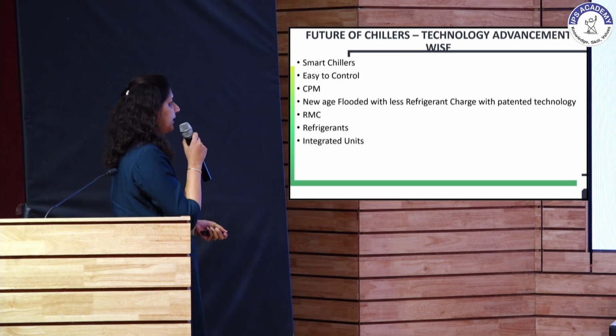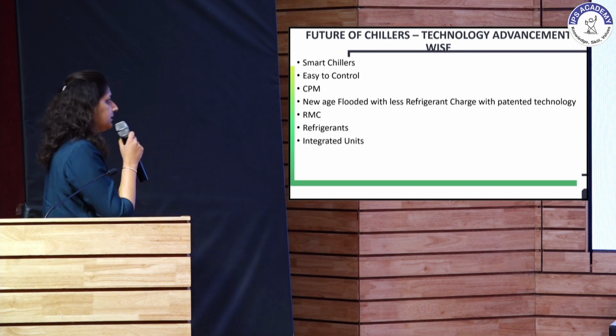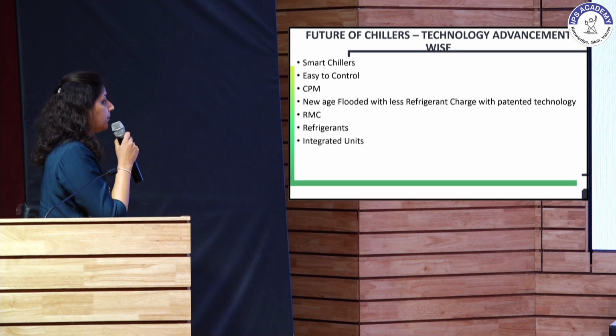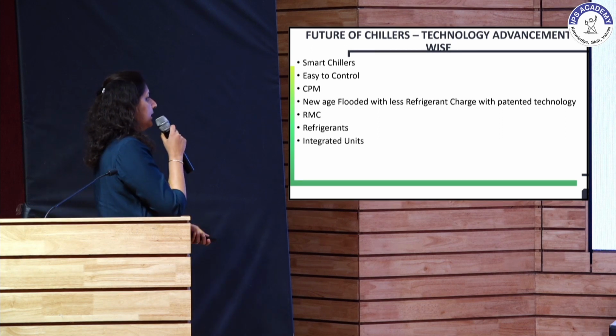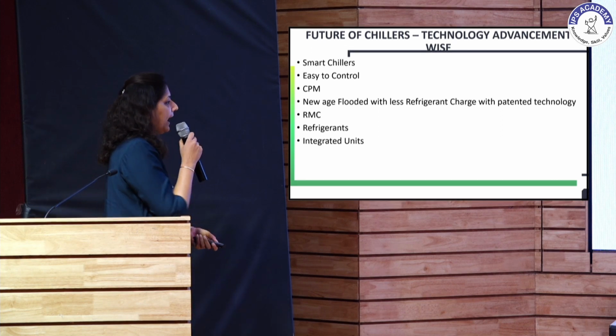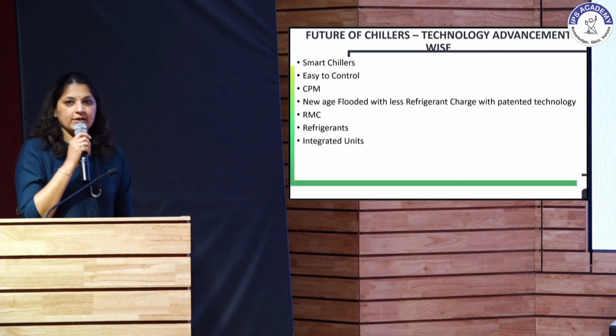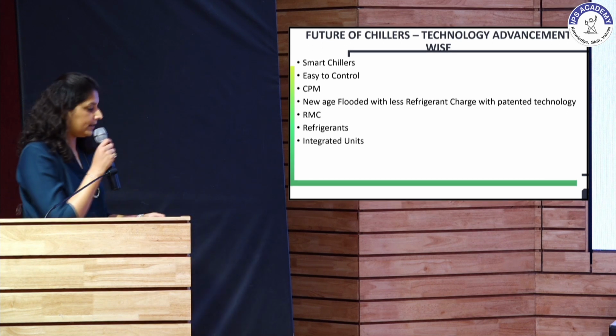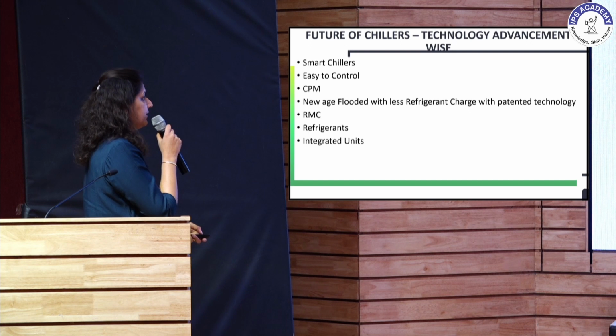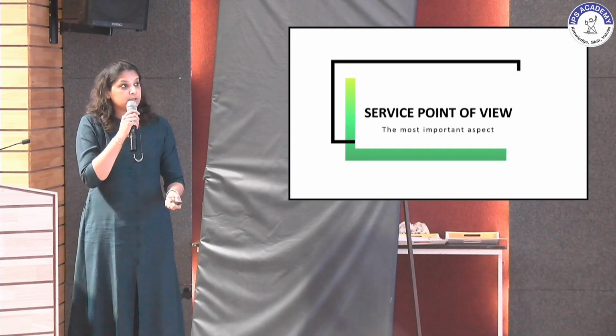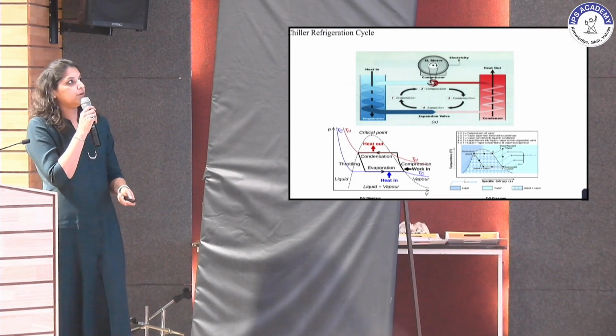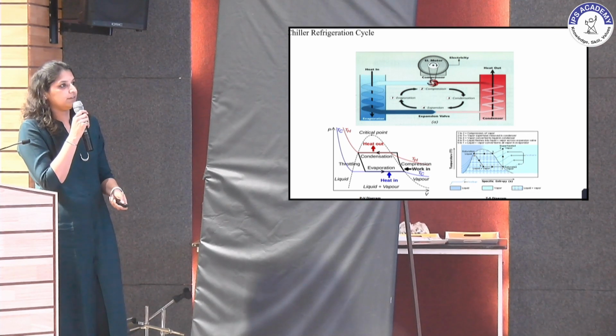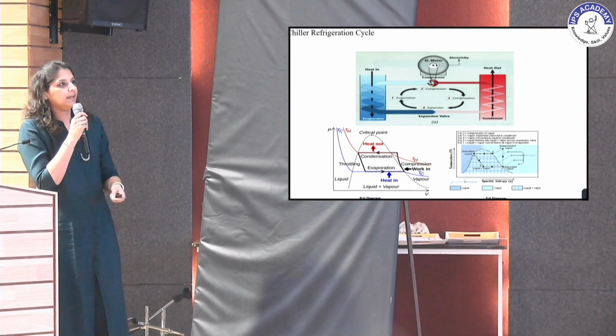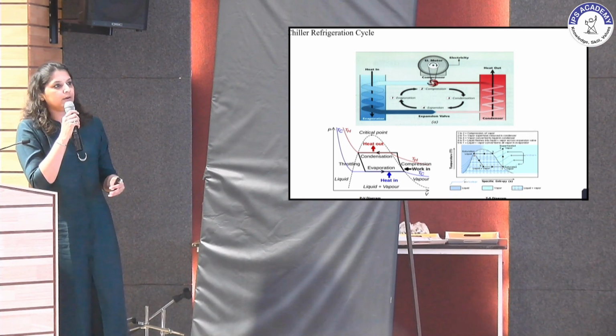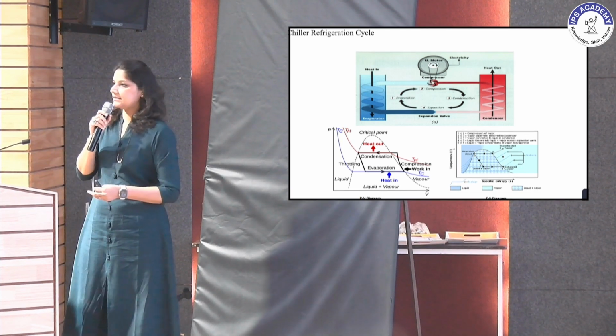New age flooded chillers with less refrigerant charge and patent technology are also available. Remote monitoring of chillers is possible now, and majorly all the green refrigerants can be applied on the chillers wherever required. So from a service point of view, we have to see the refrigeration cycle in a way that what is going bad when we are servicing it.